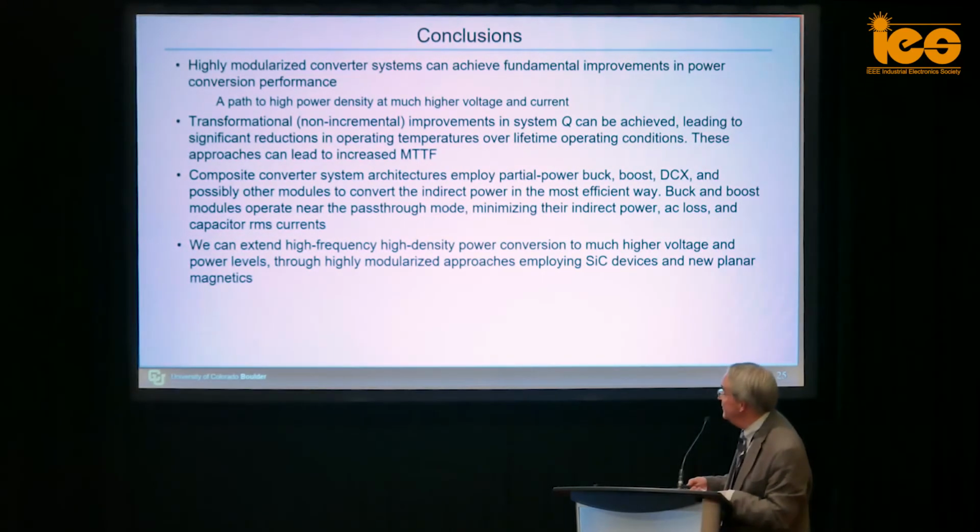Okay, so in conclusion, I claim highly modularized converter systems lead to fundamentally better performance, and really, they provide a path to high power density at new levels of voltage and current in our switching converters, and I think are a good way to go for 100 kilowatts and above. We can get improvements in the system efficiency, or Q, that lead to significant reductions in operating temperatures, and those then greatly improve our reliability.